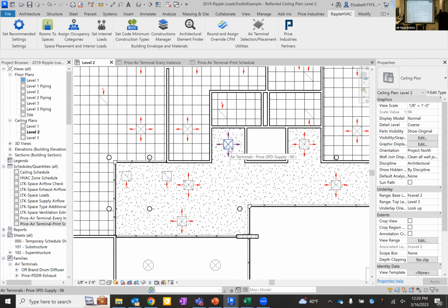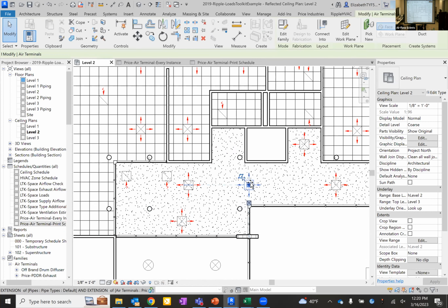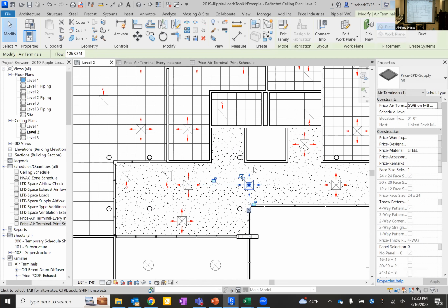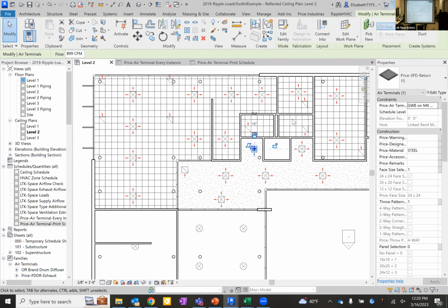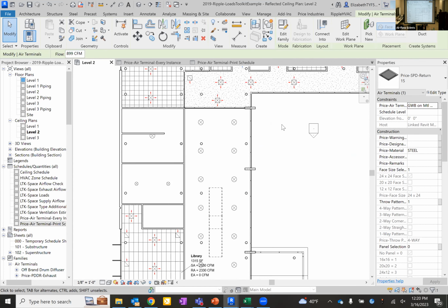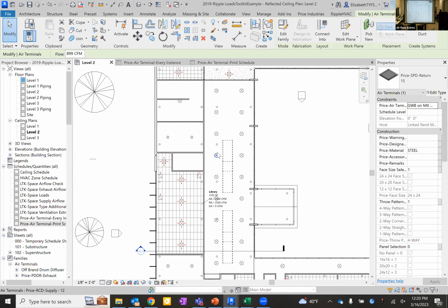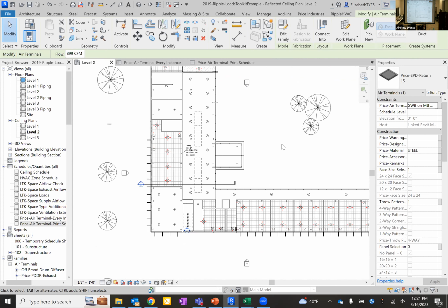Believe it or not, the goal of the tool is not to get rid of your job as an engineer. We're trying to help expedite the process and get you about 70–80% of the way there. The way this is laid out, I would not say is the end and you can send it out for plans. It will need some adjustments. You'll probably need to grab that diffuser and maybe move it out to the middle of the room, make it more intuitive. We probably don't want these two returns next to each other, so maybe we put the return in there. You have to use your engineering brain still and make some adjustments, but it will get you a majority of the way there. It's pulling out a lot of the copy and paste of diffuser selection. So this library here looks pretty good. We're pretty staggered throughout the space. Again, it gets you close, but it's not perfect.